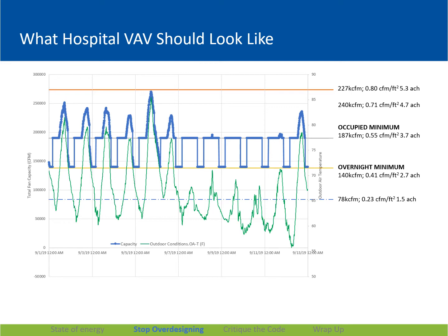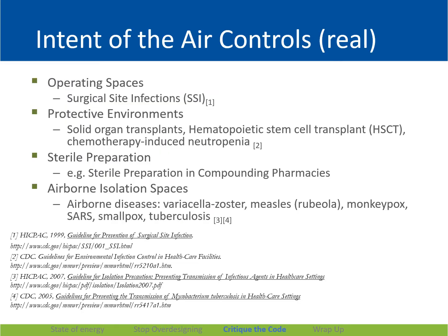Yeah, and I focused on air here because air really sets the demand. If you design an air system that turns down to 40% every night, then you'll see the chiller and the boiler energy and the reheat energy follow that, of course. So that takes us into the second part of this presentation, which is the critique of the code, or the critique of our national standard.